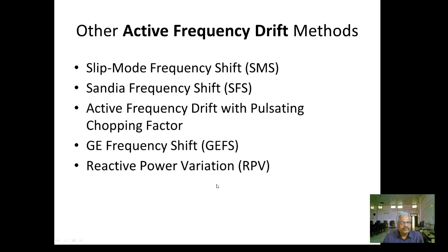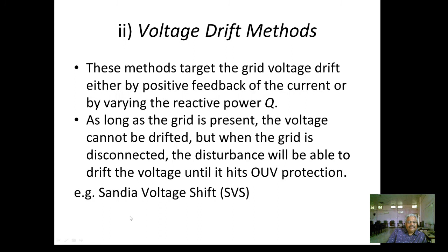Next is the voltage drift method. This is again an active method. This method targets the grid voltage drift either by positive feedback of current or by varying the reactive power. As long as the grid is present, the voltage cannot be drifted. But when the grid is disconnected, the disturbance will be able to drift the voltage until it hits the over/under voltage protection. An example is Sandia voltage drift. This is the second method of active islanding detection.